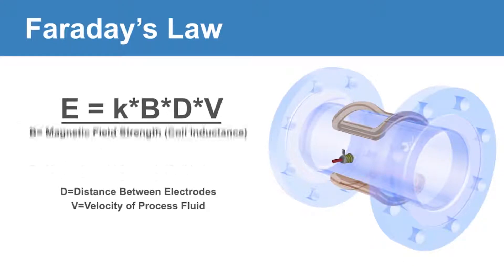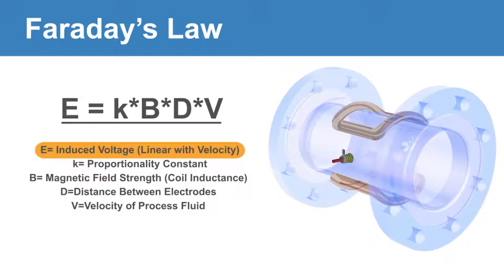This flow principle is known as Faraday's law, mathematically defined by the equation E equals K B D V, where the induced voltage, E, is directly proportional to the velocity, V, of the fluid moving through the magnetic field, B.